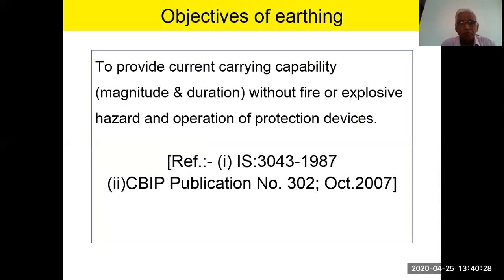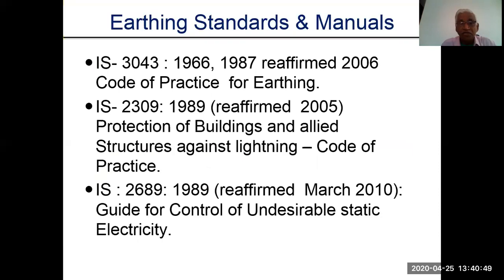Objectives of earthing: to provide a current carrying capability, in magnitude and duration, without fire or explosive hazard, and operation of protective devices. This references IS 3043/1987 as well as CBIP publication number 302, October 2007. Now we have a lot of standards in this. They are all listed here.